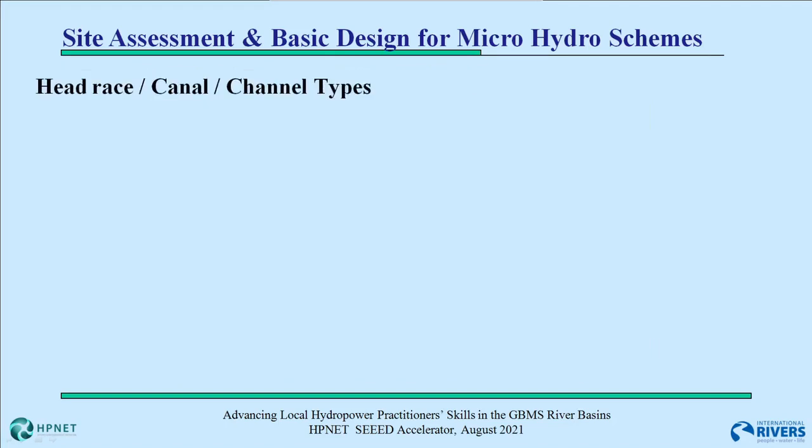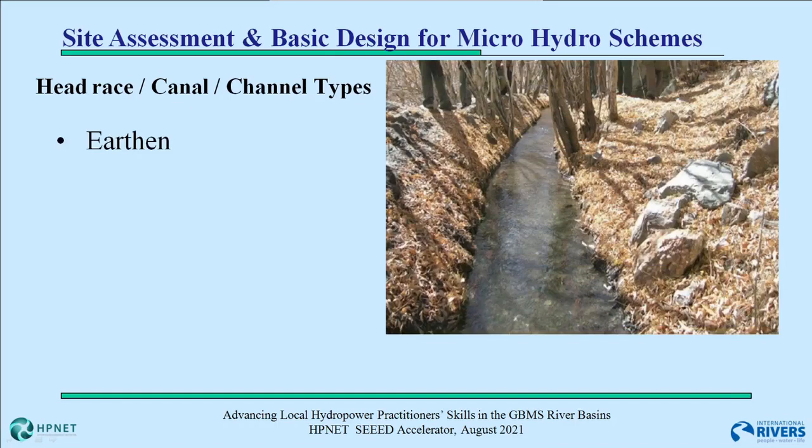Canal can be a low-cost method of conveying water from a source to a more favorable intake position. For some sites, this can really improve the economic viability by reducing the length of penstock and cable required. But at some other sites, canal is an expensive addition and can often require regular maintenance due to leaks, soil erosion, and landslides. The canal should be able to pass the design flow rate.